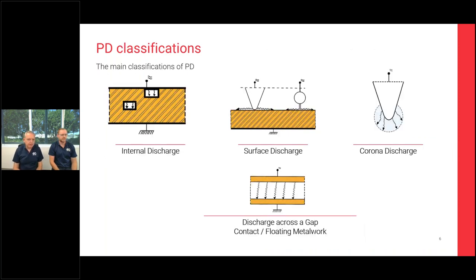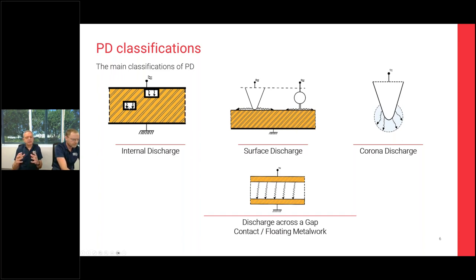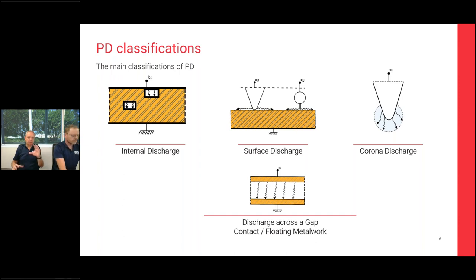Recapping the main PD classifications — they behave very differently, are measured differently, and produce different PRPD patterns. For internal discharge, there are two cavities shown: one in the center of the insulation and one close to a conductor. A discharge in the center produces a PRPD pattern occurring on both halves of the sine wave cycle quite consistently. If the void is towards the high-voltage or earth conductor, the PRPD pattern will be dominant on one half of the cycle only.